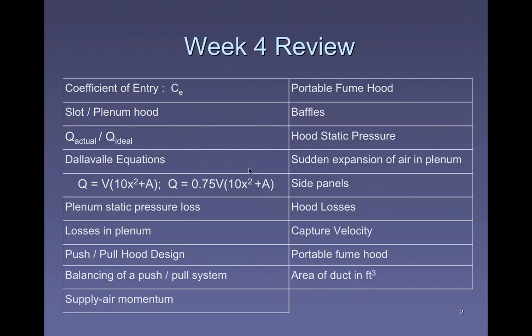These equations, the Dallavalle equations, the chart, was it chart 11, where we have all the hood equations. We started to talk about that, talk about static losses. We talked about the other kind of hood, where you supply air, you blow air across the table and you suck it in the other side. Here they're just mentioning that in push-pull design, you have to balance it. You have the same amount of air going across as you're pulling away. Otherwise, you're blowing air too fast and you're defeating the purpose of the suction on the other side. Balancing of these systems is supply air.